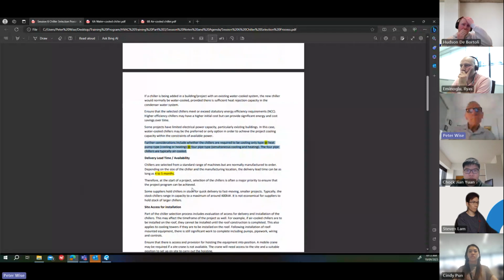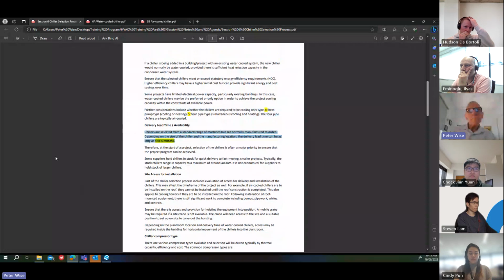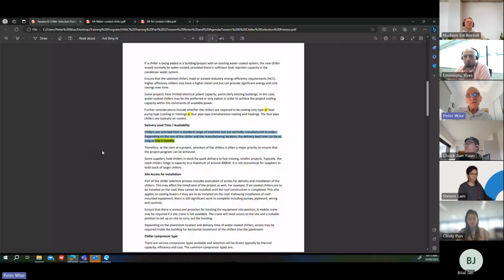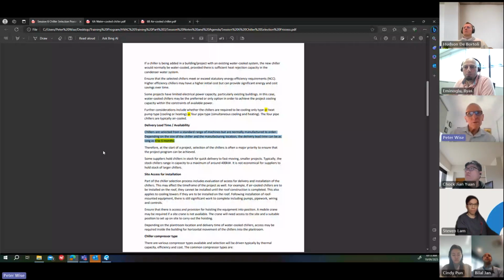Now, delivery lead time. This is another important thing to be aware of. Chillers are selected from a standard range, so you'll look up the data for what's offered in the standard range of chiller, but they're normally manufactured to your order. So if you want to order a chiller, they won't have one sitting around waiting for you. They'll have to make it. Depending on the size of the chiller and the manufacturing location, the lead time can be as high as 4 to 5 months.